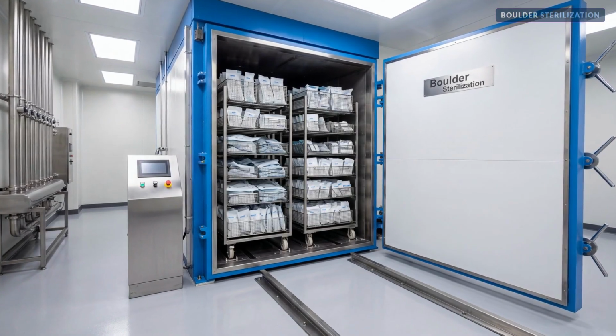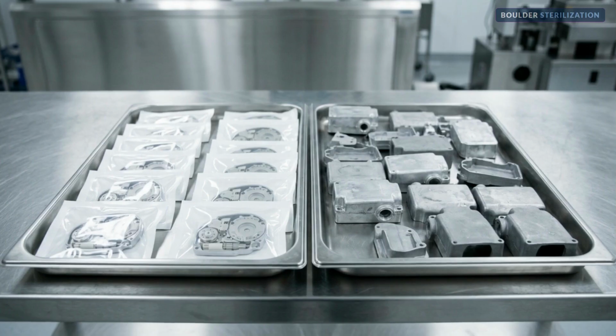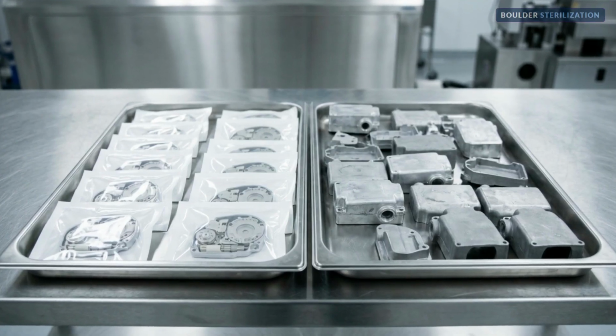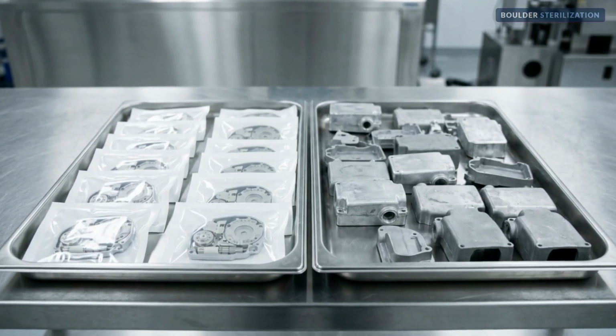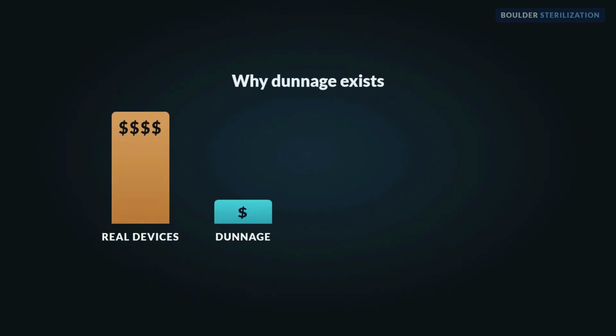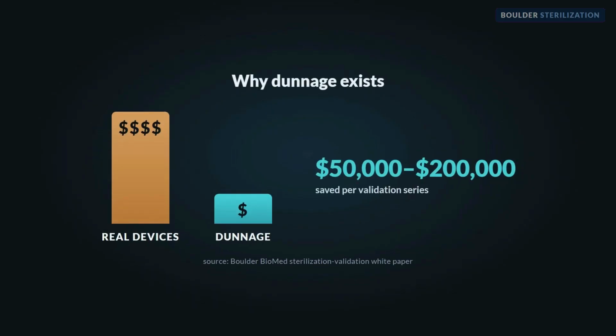The product absorbs the sterilant gas, it absorbs the moisture, it acts as a heat sink, and packed in tight, it blocks the gas from circulating. So the rule is simple. You validate the worst case, a full chamber matched for mass and density. But filling that full chamber with thousands of finished sterile-grade devices is often cost-prohibitive. And early on, when your yields are low, it can be flat-out impossible.